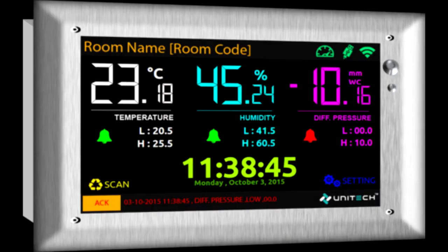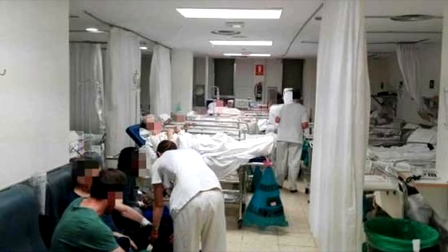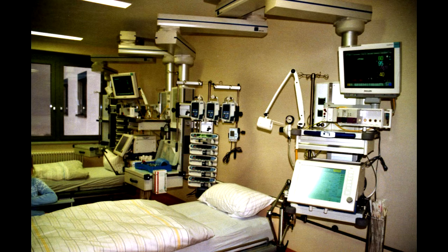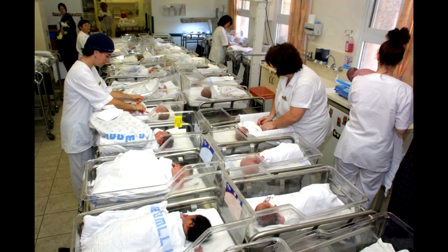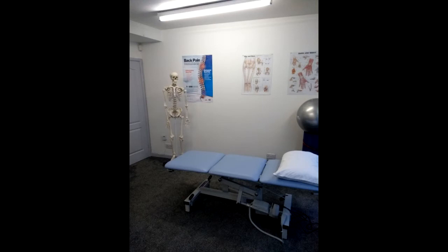While the temperature range for humans between the maximum and the minimum is 10 degrees Celsius, healthcare institutions have specific requirements for temperature within rooms. For example, adult and pediatric wards, boxes, procedure and wound dressing rooms, intensive care wards, and doctor's room have a requirement of 22 Celsius, while newborns wards, operational and obstetric theaters, physiotherapy premises, bath shower rooms have 25 Celsius.